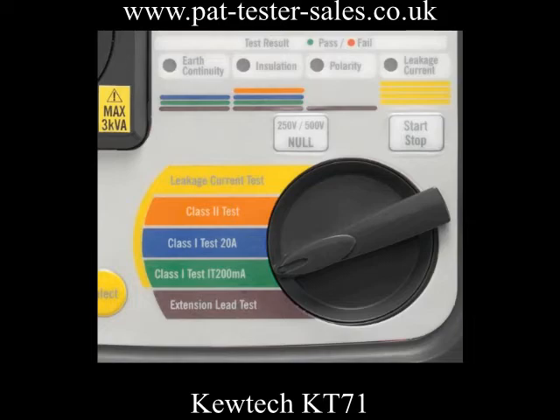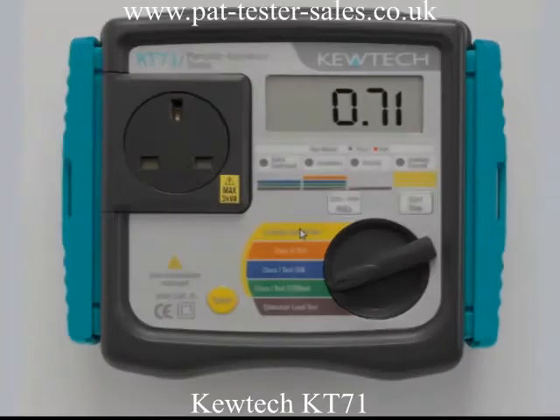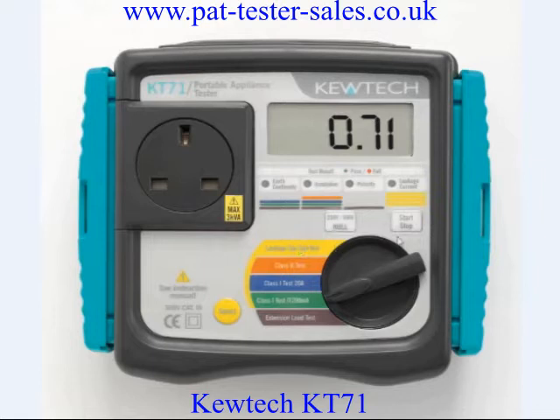All five of these are auto sequencing. As soon as you select which test you want and press the start button, the extension lead test will carry out an earth test, an insulation test, and a polarity test.